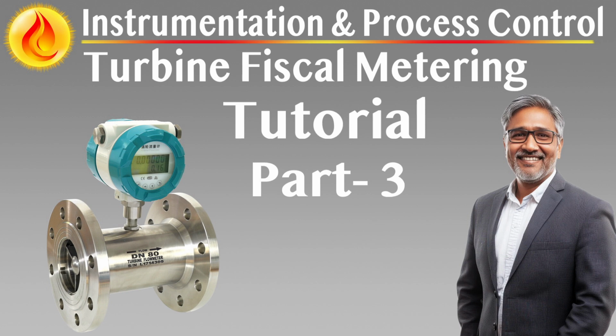Sampling must occur at constant pressure to preserve fluid homogeneity and avoid phase separation. The system must include temperature control via heat tracing or insulation as needed to maintain a stable viscosity and prevent sample stratification or wax dropout, especially for heavy crudes. The sampler's collection container must be designed for easy removal and transportation to a certified laboratory with appropriate sealing provisions to prevent tampering.